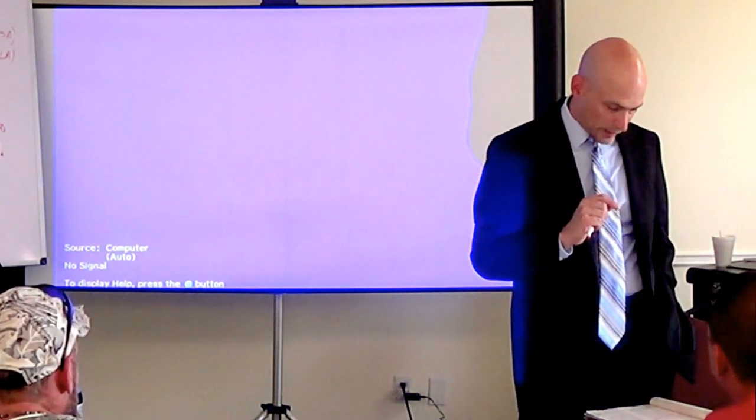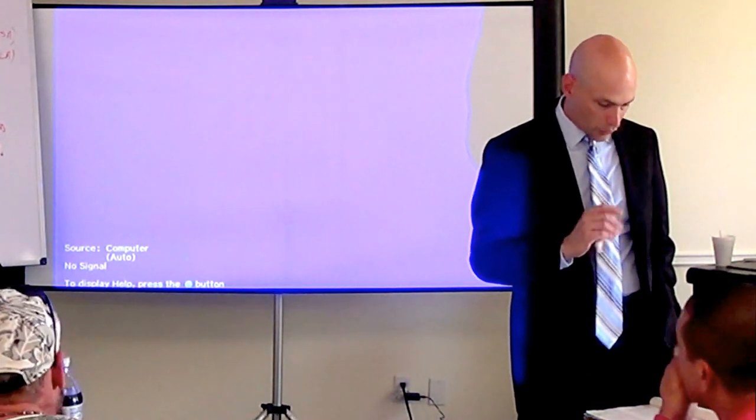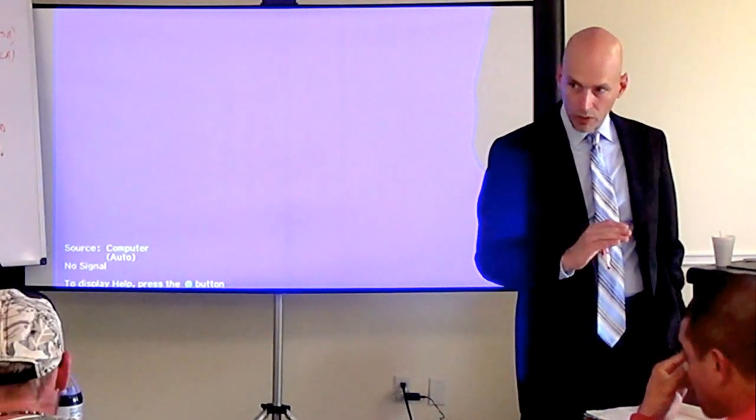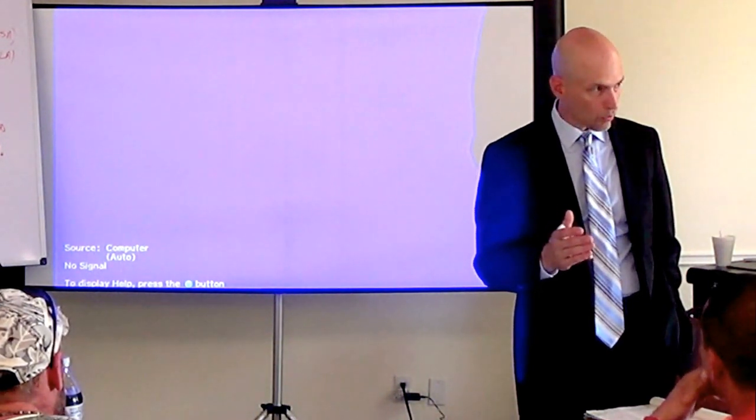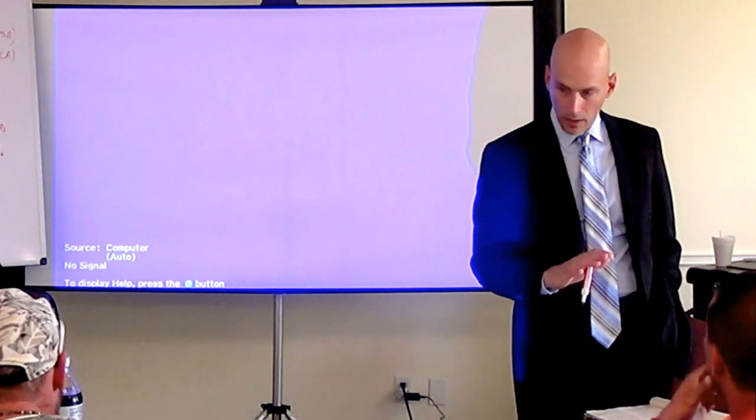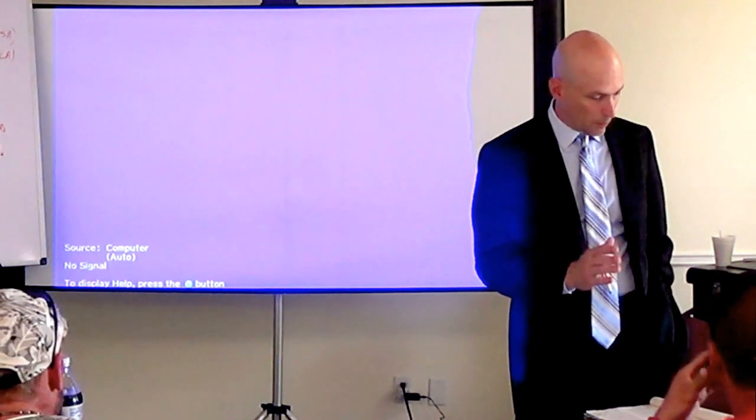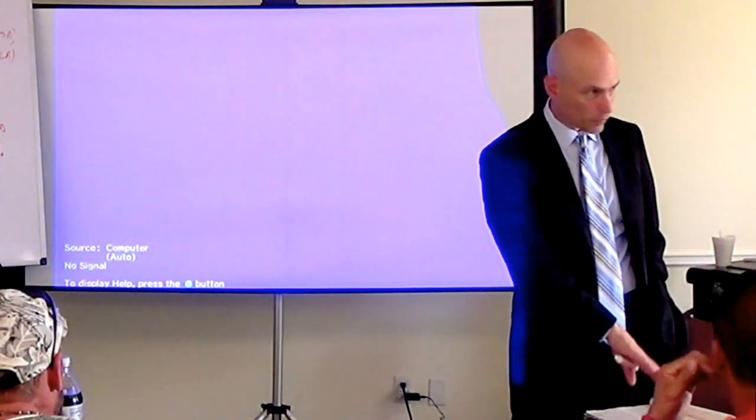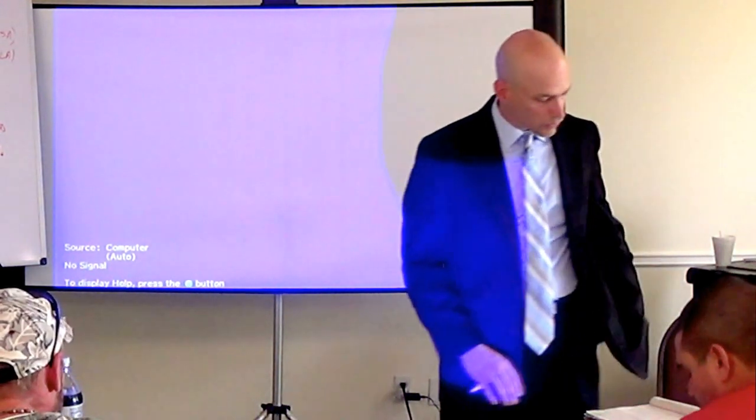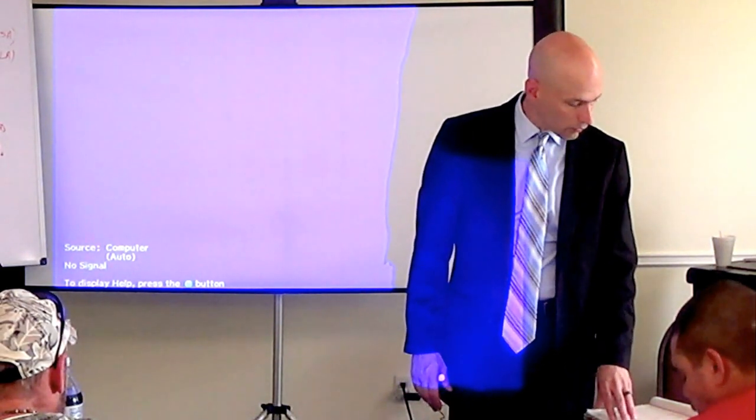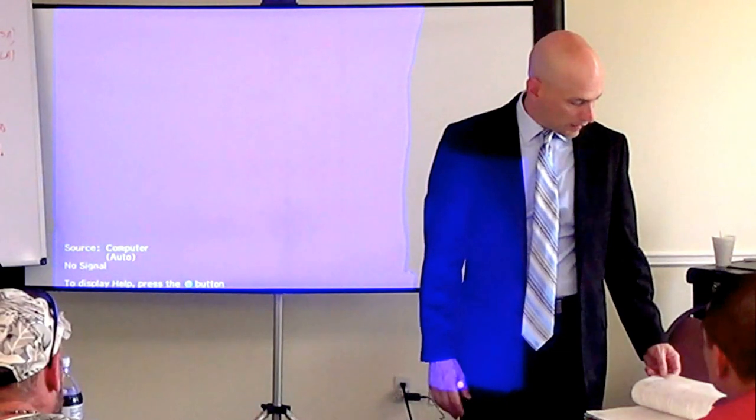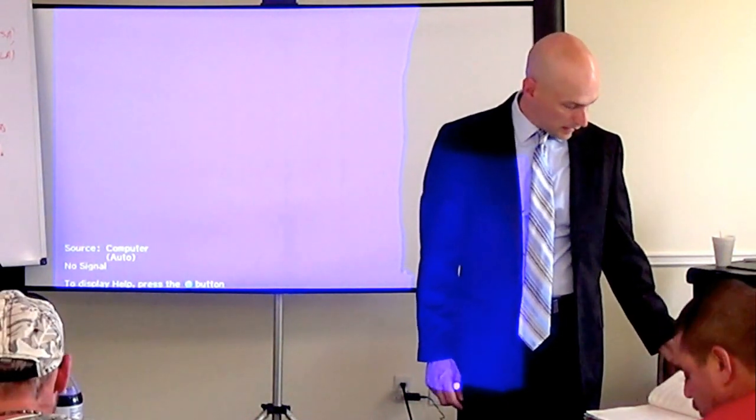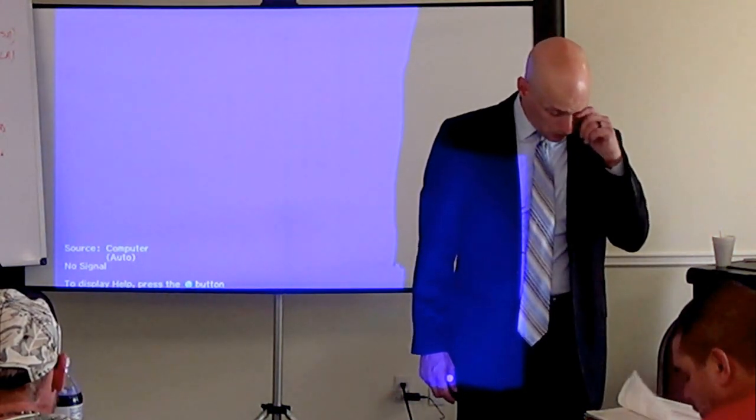Now, the one thing is under standard method, under part three, we take a 25% increase on the largest motor in the group. Right? That is a separate and distinct part than what we're under here. So unless there's clear directions under this article, that's not part of this step. And there's nothing in here that could give us any kind of rule to do that.